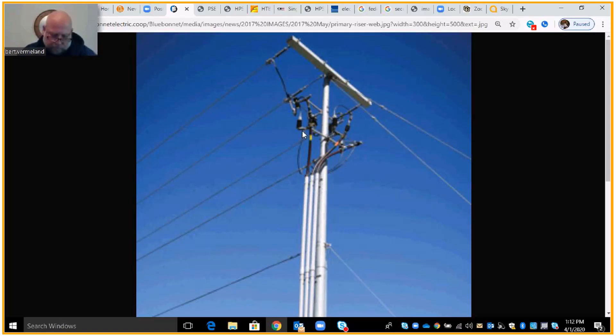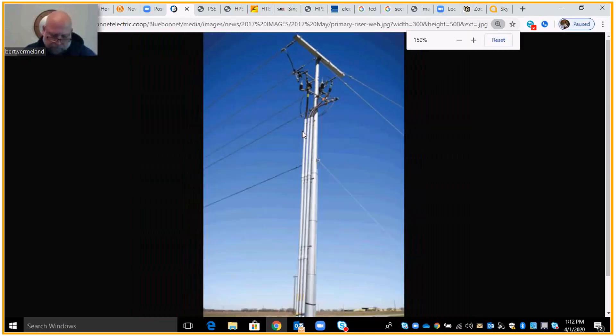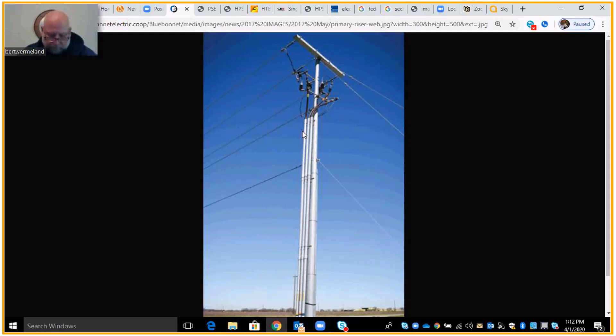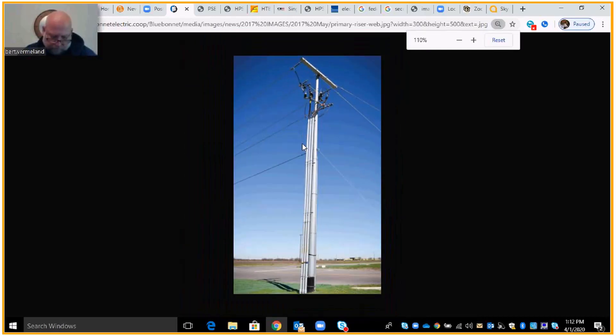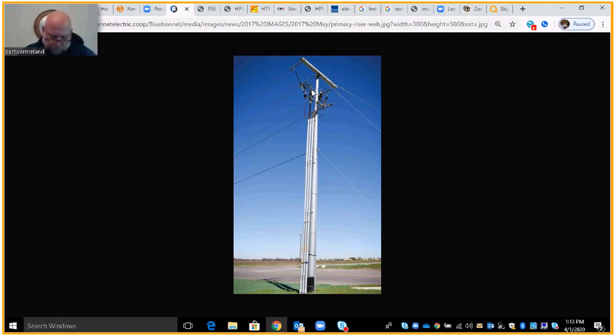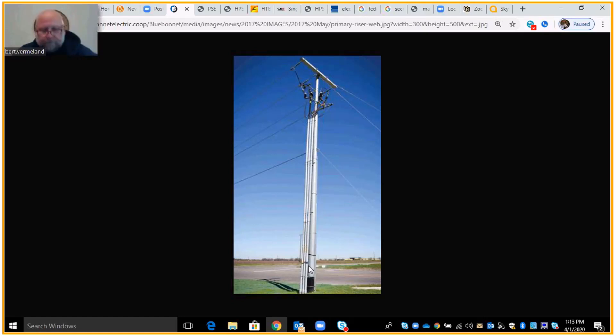In some cases, like the substation we toured, the underground primary wires go out of the substation, come underground, go out to Highway 501, and then go overhead — that is called a riser. So if my feed direction comes from the substation to the pole and then out overhead, that is called a riser pole. If underground is fed from overhead and goes to a transformer or wherever it needs to go, that is called a dip.